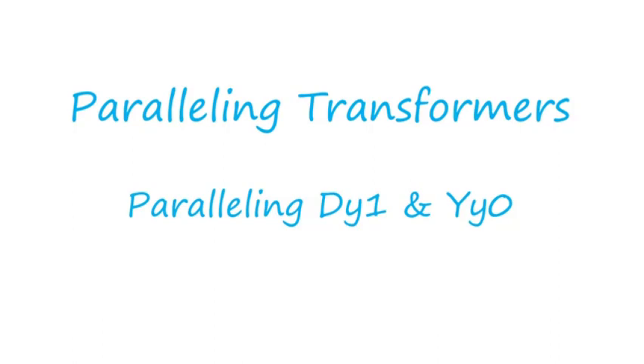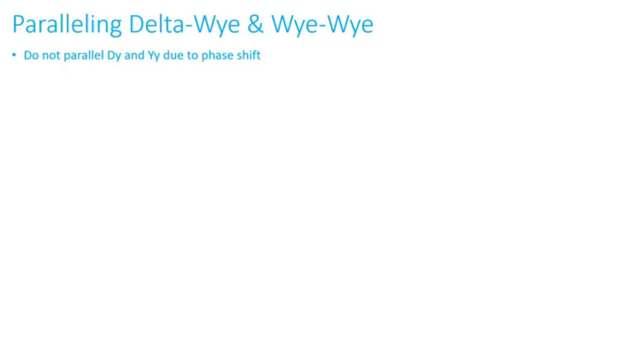In this video I'll continue the discussion on parallel transformers. I'll show what happens when you parallel a delta-y and yy transformer where you have a phase shift between the two. You don't want to parallel delta-y and yy due to the phase shift. For instance, let's assume we have two transformers: one connected as delta-y1 where the high side is delta, low side is y, and the high side leads the low side by 30 degrees. The other is yy0, meaning the high side is grounded y, the low side is grounded y, with no phase shift.